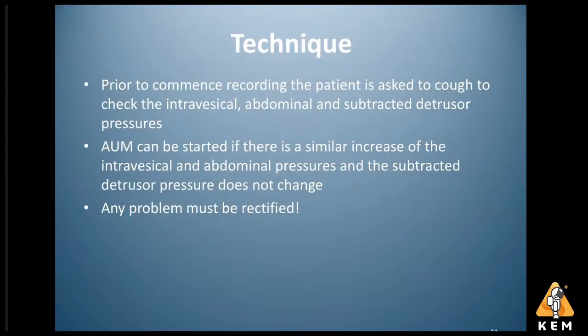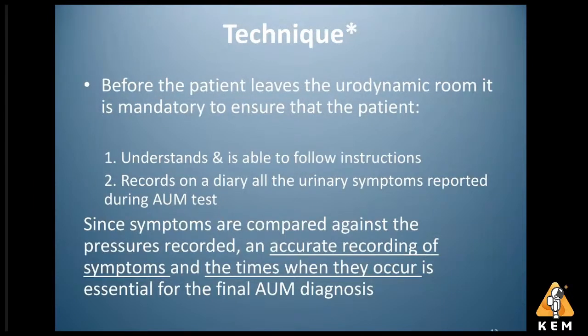Prior to commencing the recording, the patient is asked to cough. This is part of calibration, and to check the intravesical and abdominal pressure and the subtracted detrusor pressure. The ambulatory urodynamic machine can be started if there is a similar increase of the intravesical and abdominal pressure, and the subtracted detrusor pressure doesn't change. If there is any problem, it needs to be rectified before commencing the study.